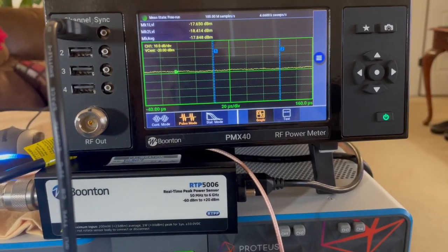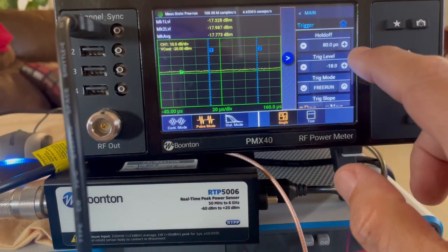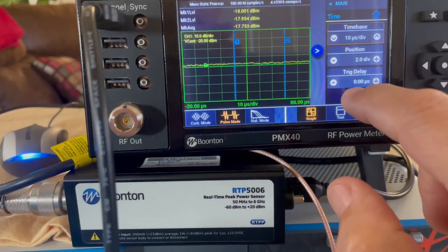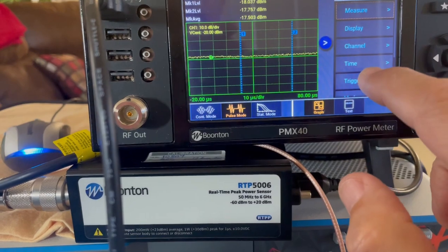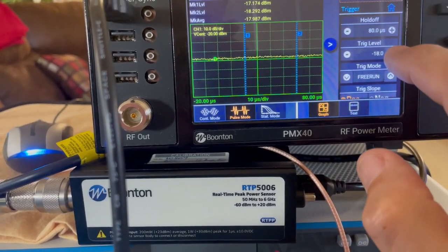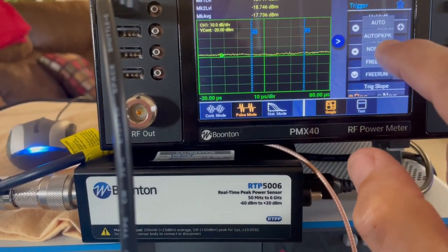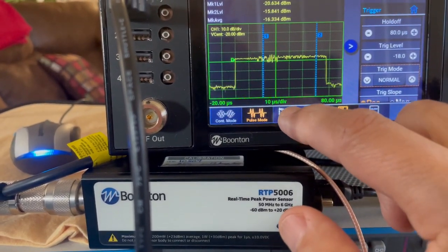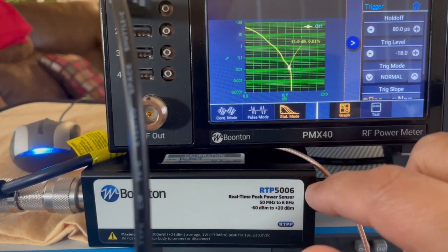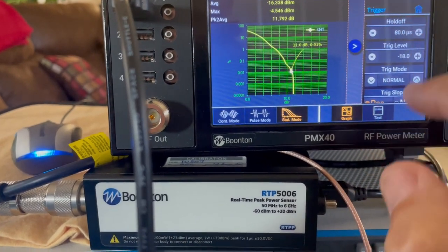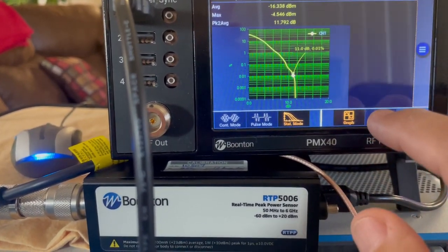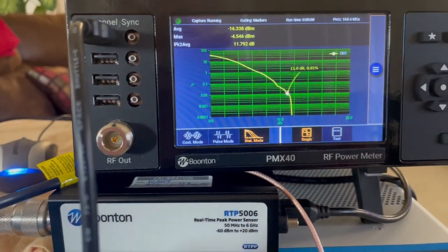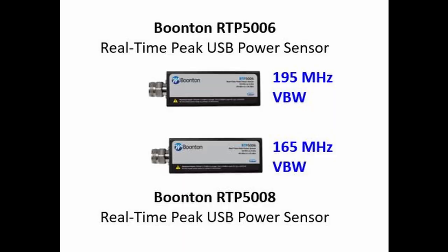The Wi-Fi 6 signal can then be measured with the Boonton PMX40 and the Boonton RTP5000 series peak power sensors. The Boonton RTP5000 sensors are the only sensors on the market with sufficient video bandwidth — more than 160 megahertz — to accurately measure 80 and 160 megahertz Wi-Fi channels. The wide video bandwidth enables users to accurately measure the entire waveform.